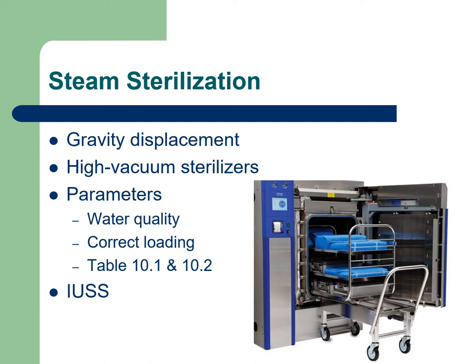Now we're going to talk about steam sterilization. There are three different types of steam sterilizers that you will come into contact with. The first one is the gravity displacement steam sterilizer. Secondly is the high vacuum sterilizer. And then last is the immediate use steam sterilizer, which we have talked about before. The big difference between the gravity displacement and the high vacuum sterilizer is how air is removed from the chamber.